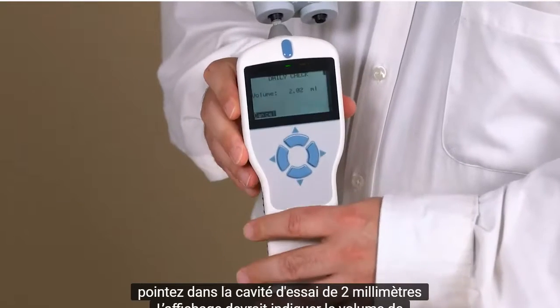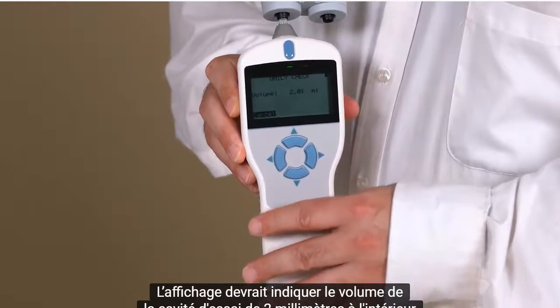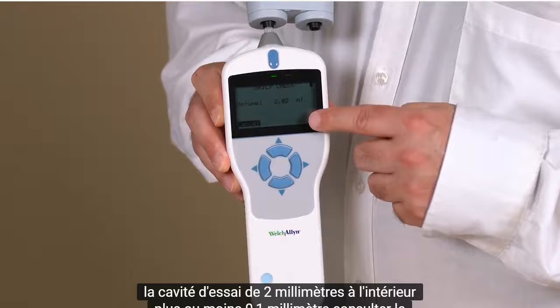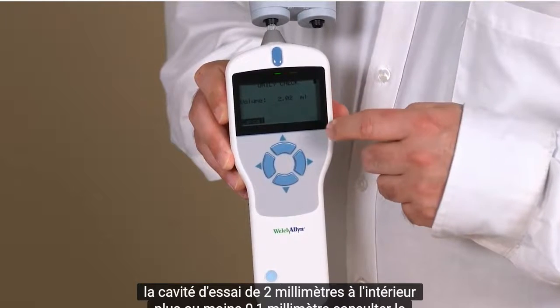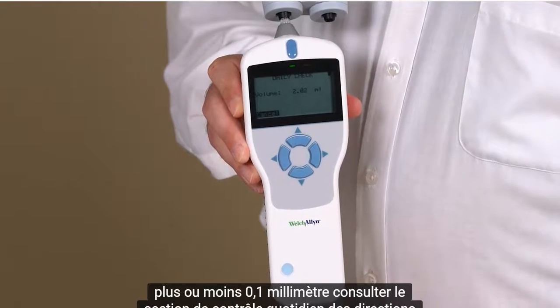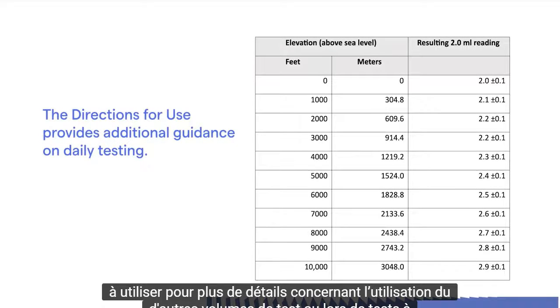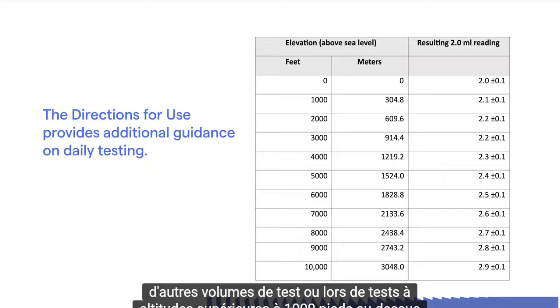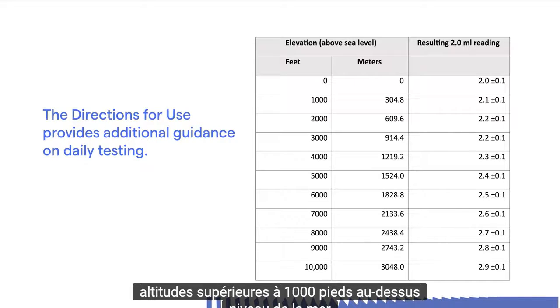The display should show the volume of the 2ml test cavity to within plus or minus 0.1 ml. Consult the Daily Check section of the directions for use for detail regarding use of the other test volumes or when testing at elevations higher than 1,000 feet above sea level.